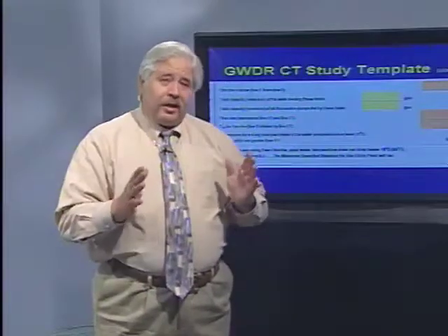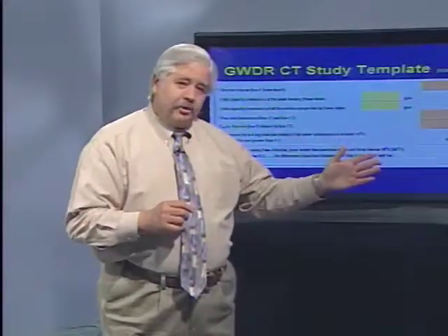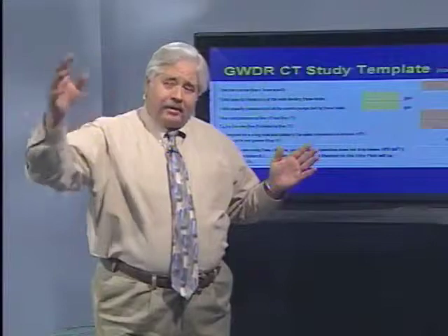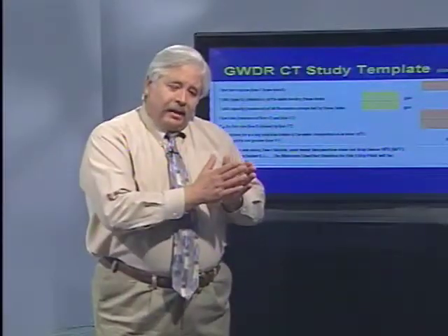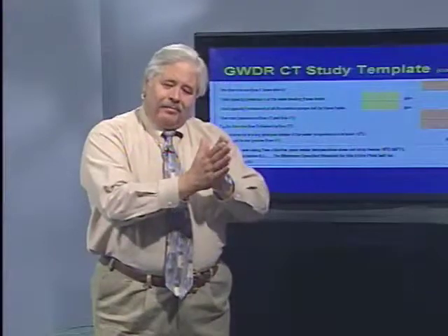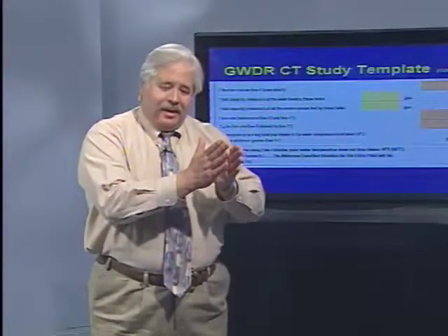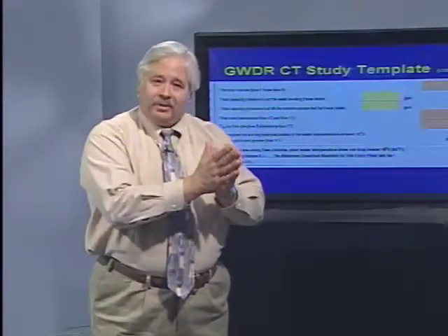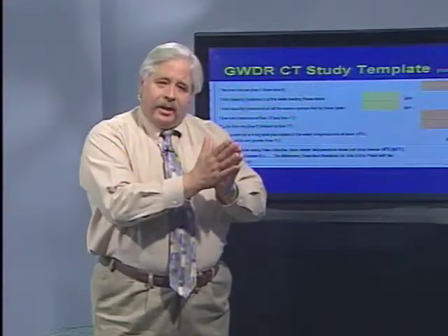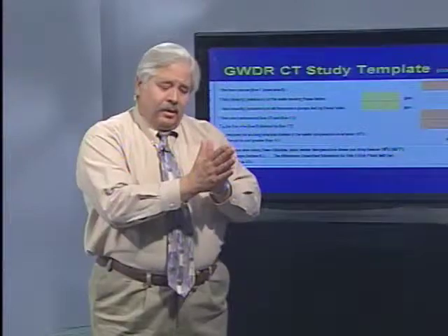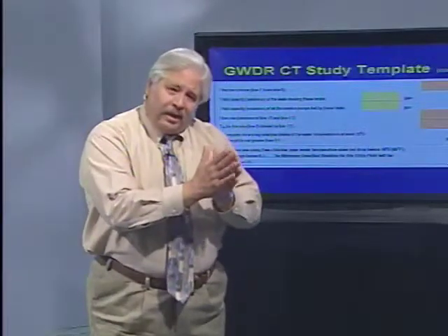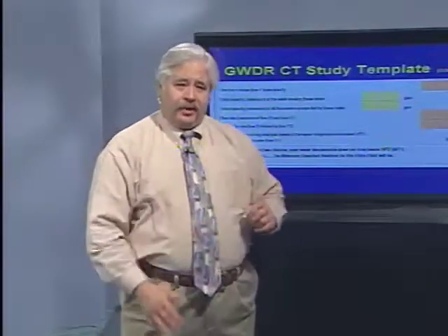But a lot of studies have been done where they inject a tracer into the storage tank and track the output of that tracer through the storage tank. And it's like when you have T10, T1% is really close to T10%. So by using a T10% value or T10 value for the contact time, we're getting pretty close to 100% disinfection.